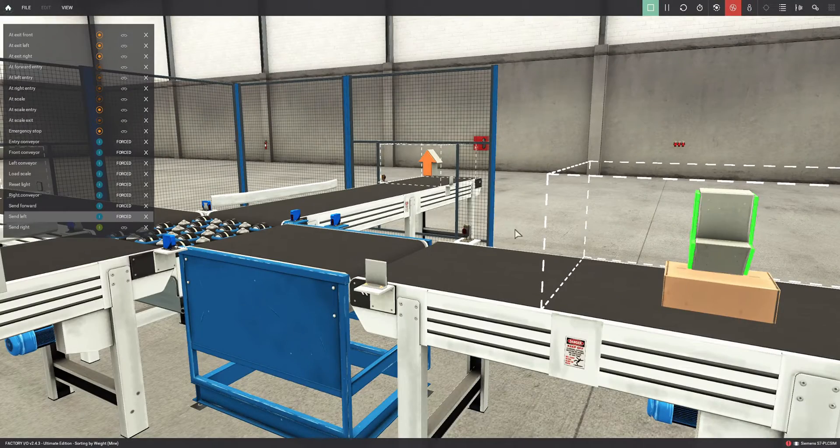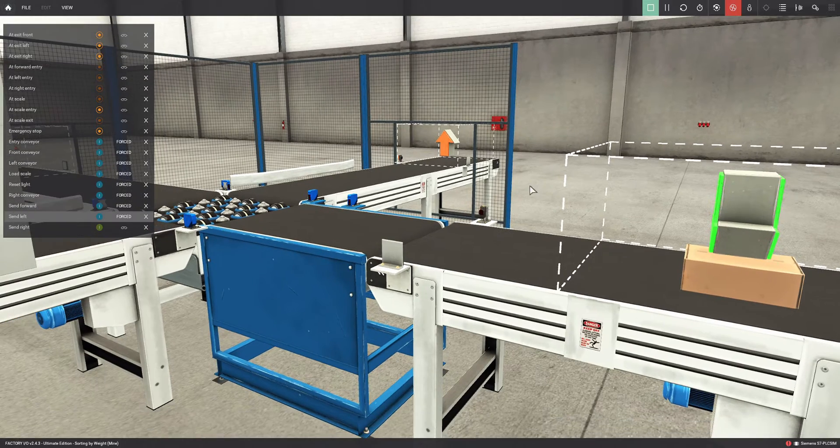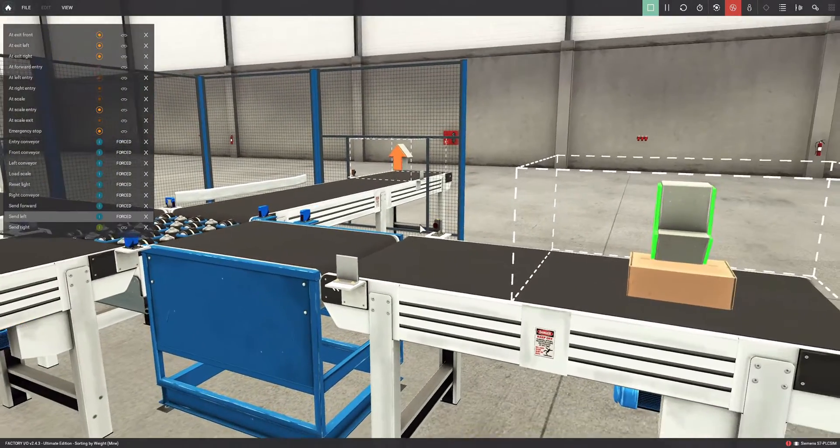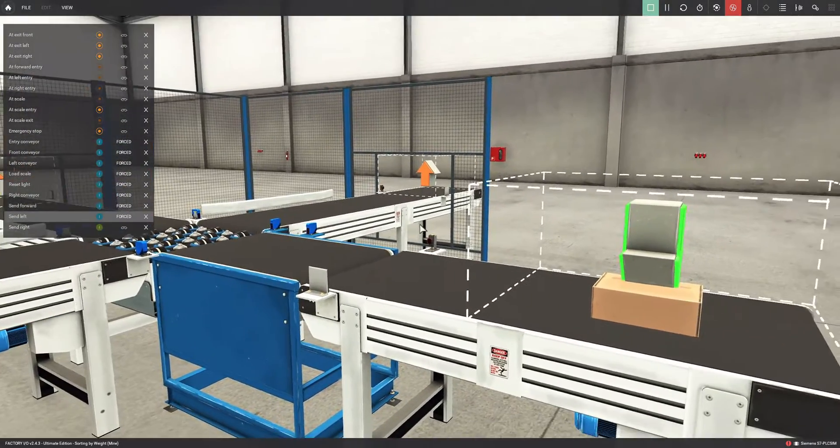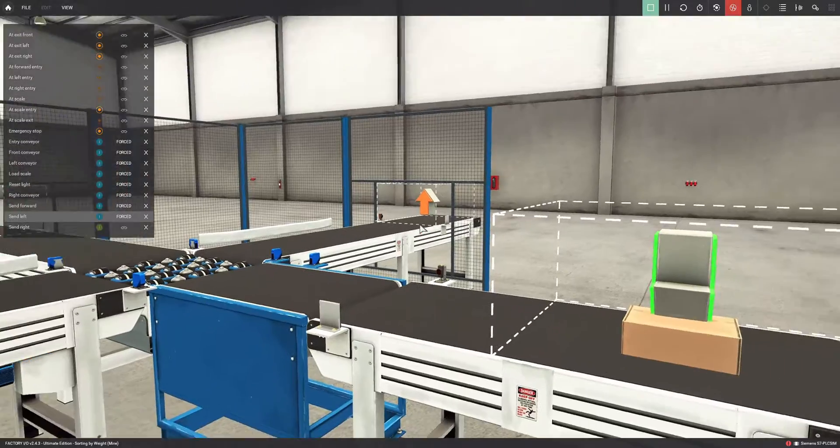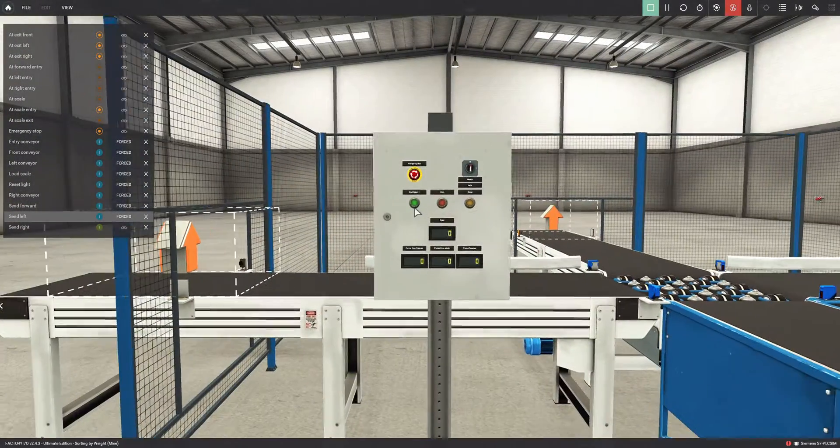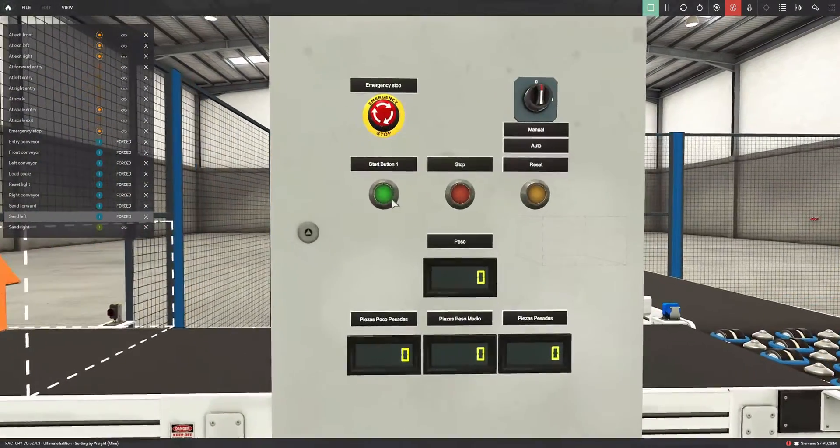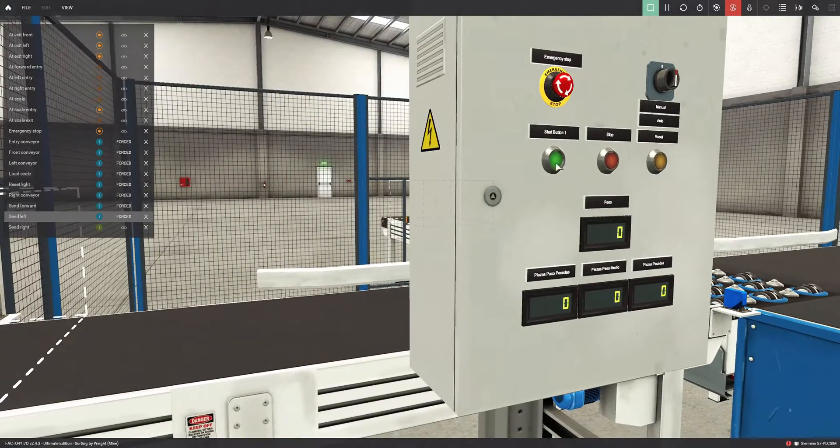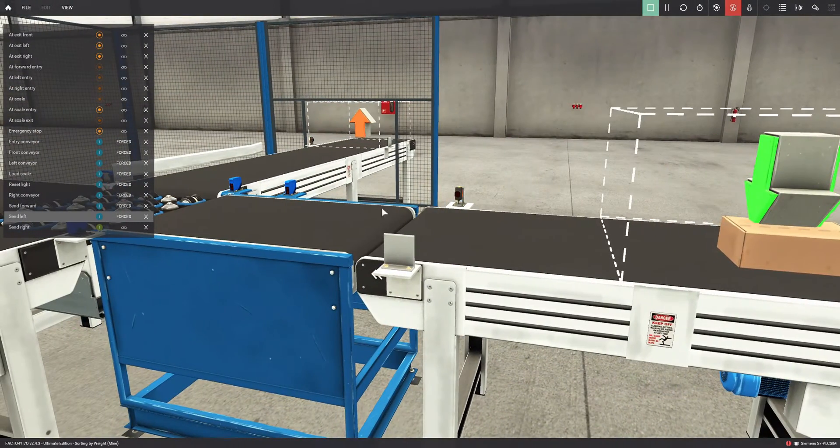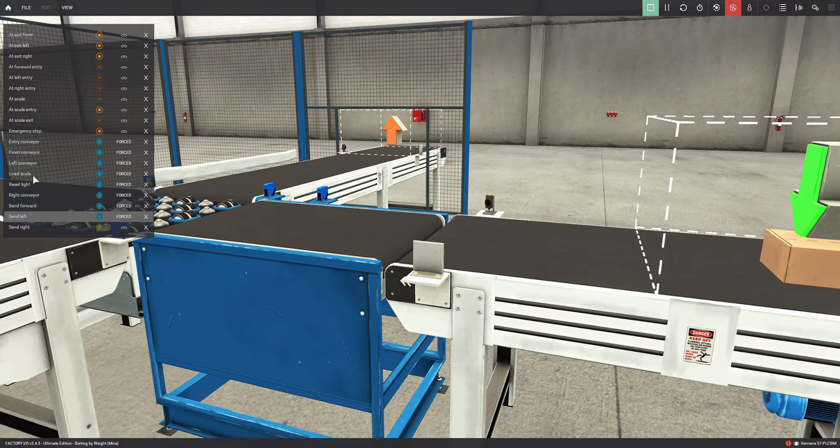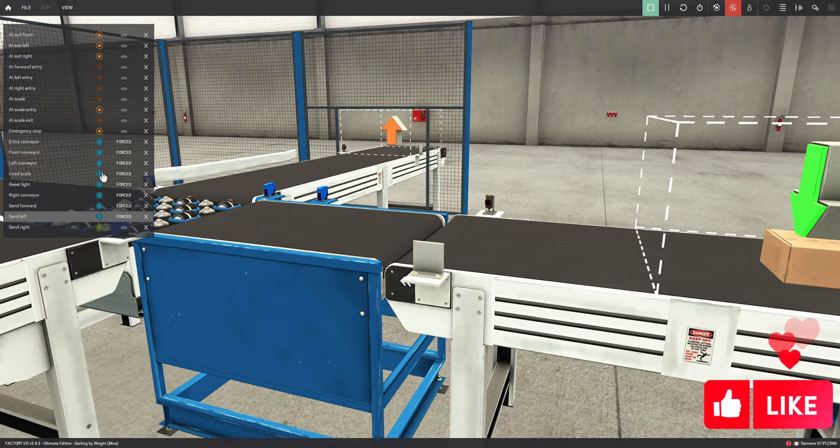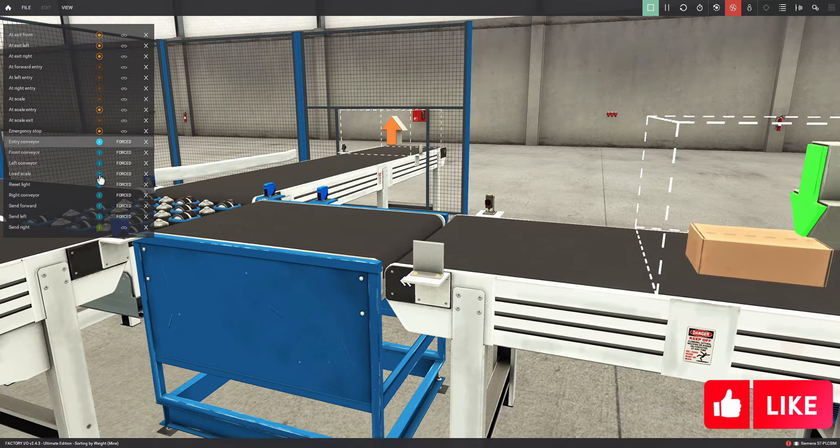Having seen the first part, now let's see how the actual operation works, the different variables we have, the sensors, the actuators. So I'll explain them to properly program this. First, upon pressing the start button, which I've configured as a switch, these two conveyors would start - both the entry conveyor and this conveyor that also functions as the scale. These correspond to the Load Scale and Entry Conveyor actuators, so we activate them at the same time.